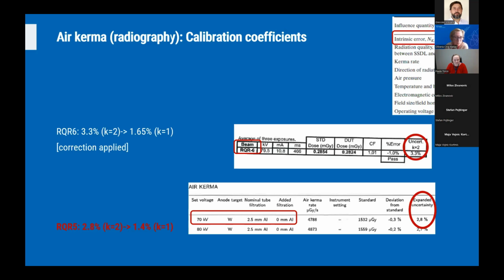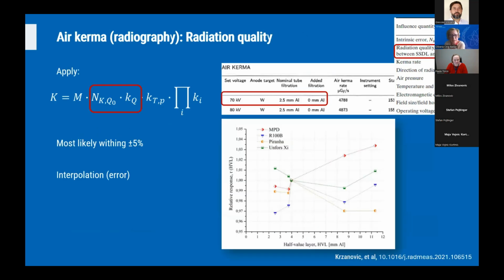There are two options when using the calibration certificate. One is to apply a correction factor to the measurement results and use the uncertainty of the calibration factor. The other option is to combine these two and increase the overall uncertainty budget due to differences in radiation qualities. Radiation quality is quite a big and important consideration when we talk about solid state detectors or dosimeters due to their very pronounced energy dependence. This was already discussed by Stefan earlier today.